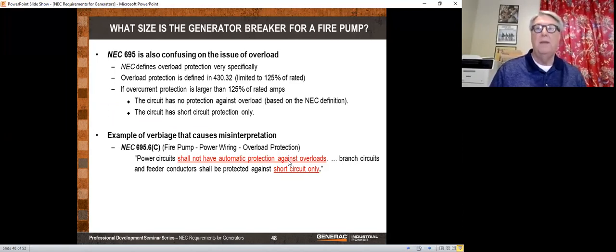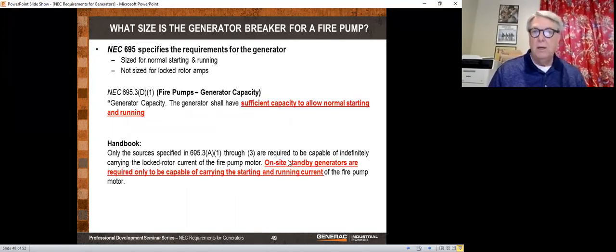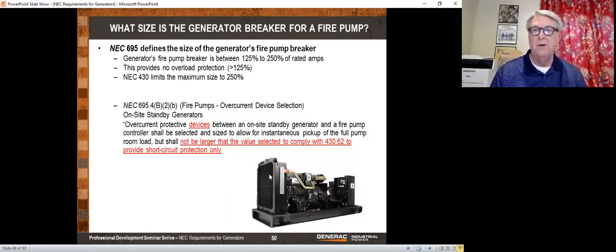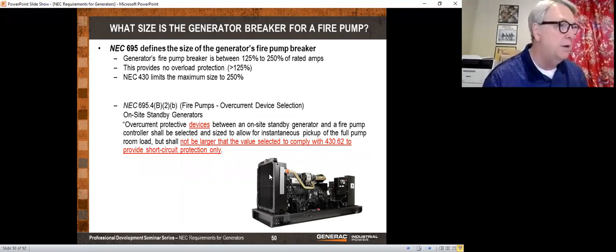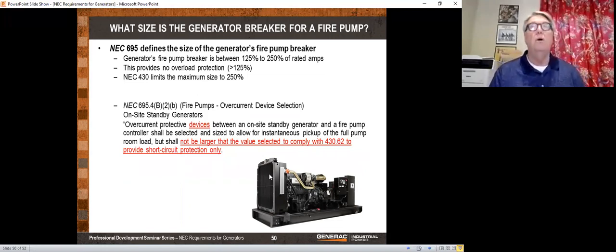And in the normal starting method, it says right here, the generator shall have sufficient capacity to allow normal starting and running. And in the handbook, it says on-site standby generators are required only to be capable of carrying the starting and running current, not the locked rotor indefinitely. So we generally have a normal starting method and a backup method, and the normal would be a VFD or a reduced voltage starter or a delta Y starter.